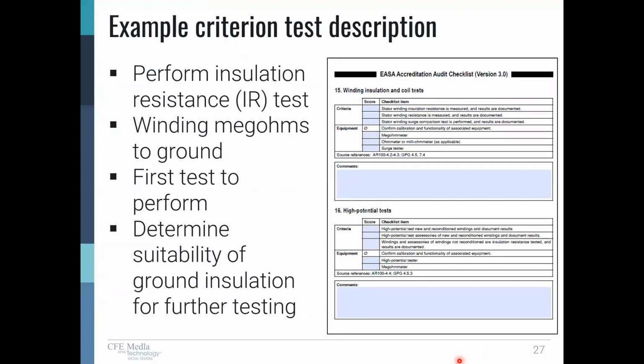Example criterion used for test in the test descriptions. This is item number 15 in the checklist, winding insulation and coil tests. And the first criteria says stator winding insulation resistance is measured, results are documented. So what's done is an insulation resistance test is performed. This applies a low voltage to the winding. The insulation resistance in millions of ohms or megohms is measured between winding and ground. It's the first test that's performed on the machine.